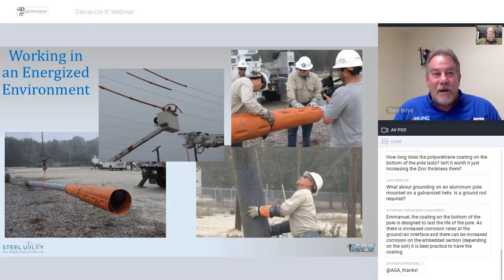I do know one occasion where, when they put so many line hose on to bring the steel pole up into that energized area, they didn't realize the amount of weight and sag that was added to it. So when they tested to see where the digger derrick claws would be, they measured it before it was rubbered. When they put all those line hose on, it actually made it sag, and the digger derrick got up and actually contacted the line hose. It did not trip the circuit out, but it made a little bit of a spark in there. And we had to stop and regroup. What we did was we actually got an extra bucket in there, lifted up on the line, and got it out of the way.